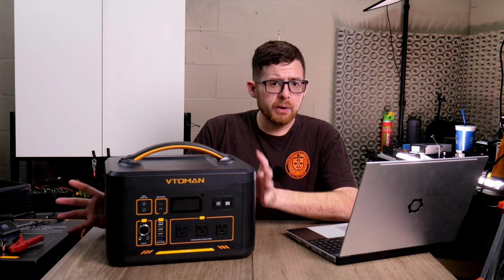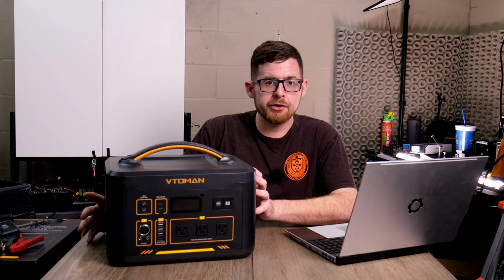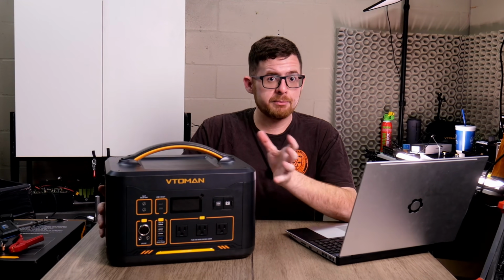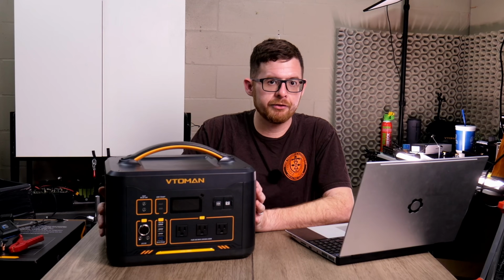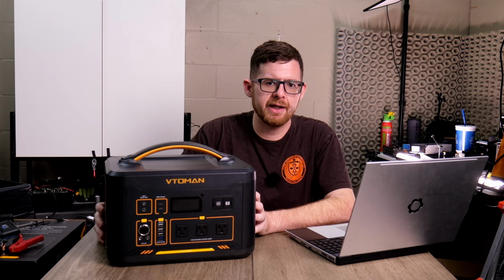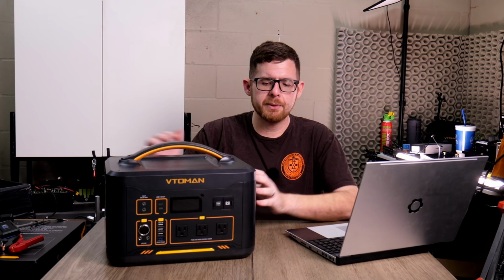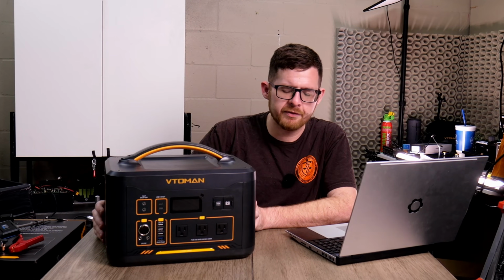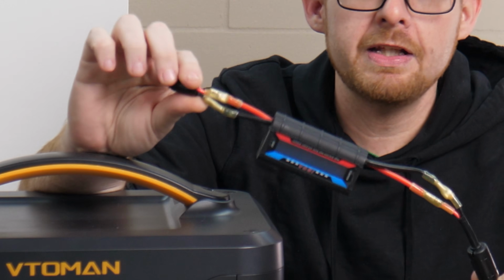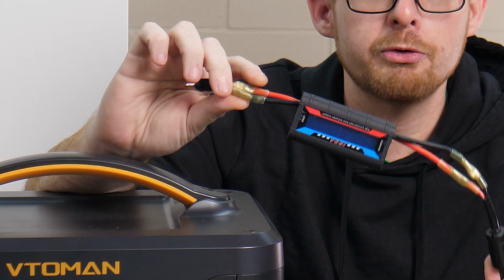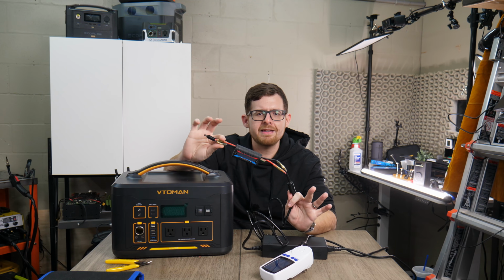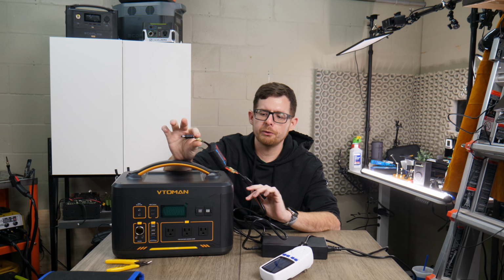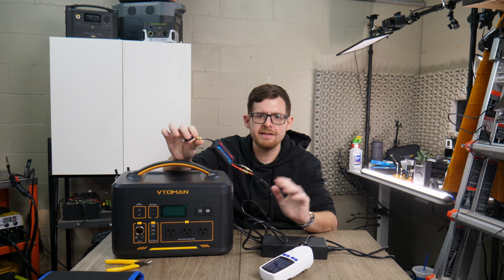So I went ahead and drained it completely, got it down to 0%, and let it sit for a couple of days to make sure it was actually at a full 0% and not just an issue with the batteries inside fluctuating below the amount the BMS would see. Then I wired up an inline shunt between the charger they provided and the DC outlet to find out exactly how much wattage was going into this unit in DC watts.